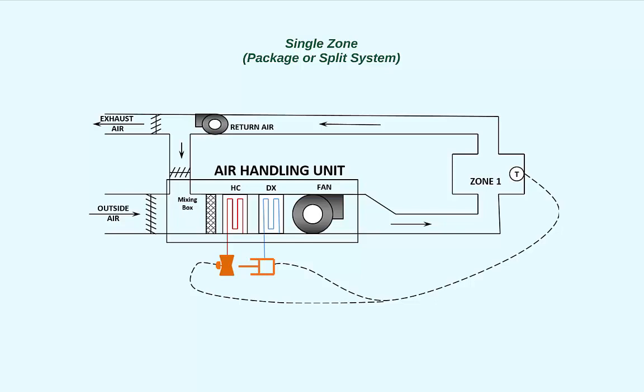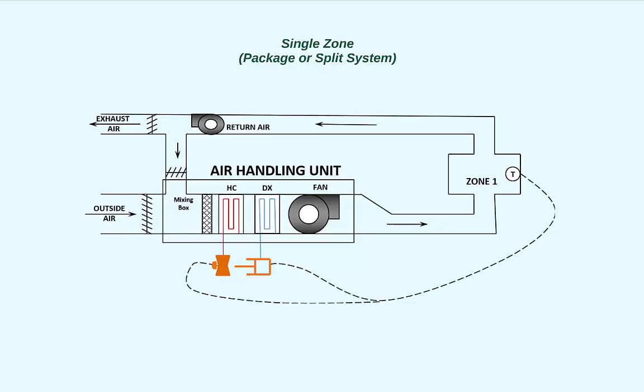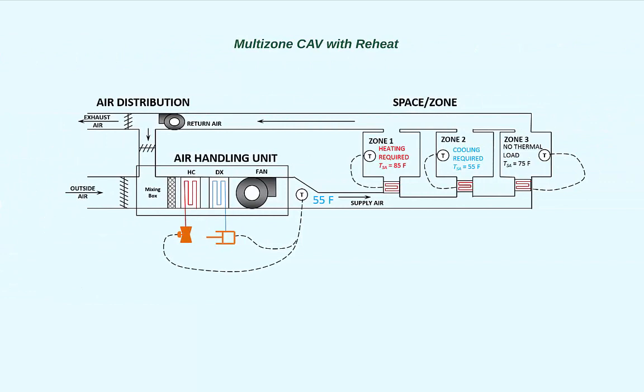Air passes over the evaporator, and the air supplied to the zone is cooled. Once the zone temperature is cooled below the control differential, the controller sends an off signal to the unit, which opens an internal relay and stops the refrigeration cycle. A multi-zone constant air volume system works very similar. The one difference is the refrigeration cycle is controlled based upon discharge air temperature. If the discharge air temperature exceeds 55 degrees, the controller will send a signal to the relay, which activates the refrigeration cycle. In this example, discharge air is maintained around 55 degrees with reheat available at each zone.